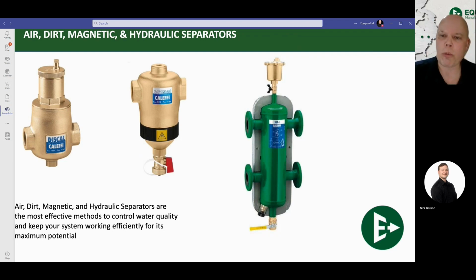The last one that you see on the right, that's called a low loss header, or hydraulic separator, and it hydraulically separates the flow from the boiler and the system. We'll talk about that here in just a moment, but essentially you can get these with built-in high efficiency air separators, built-in dirt separators, and built-in magnetics, where it can be everything you need it to be all in one piece. The fewer pieces you have, the fewer leak paths in a system.